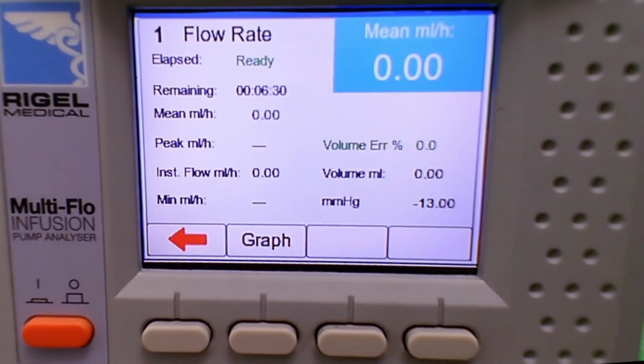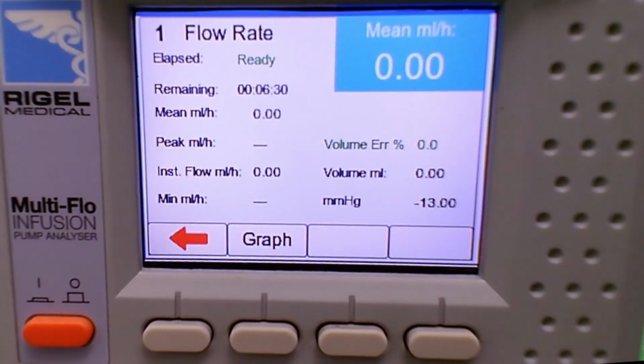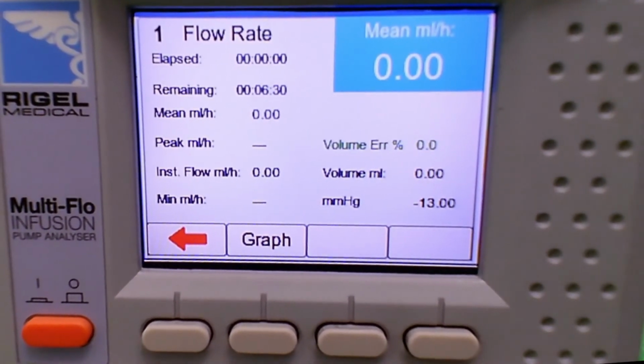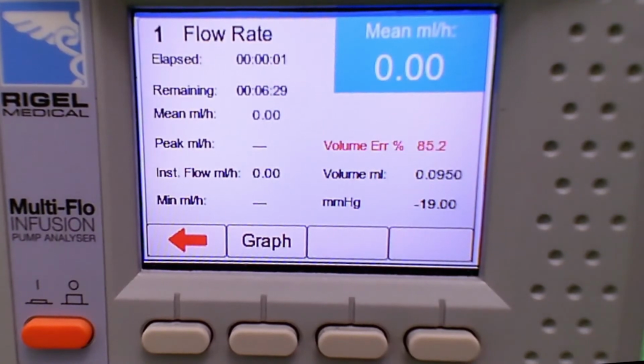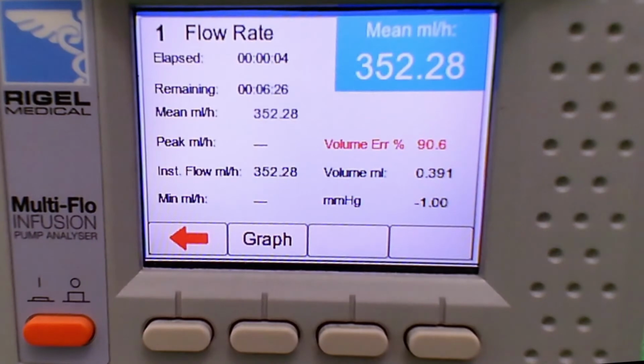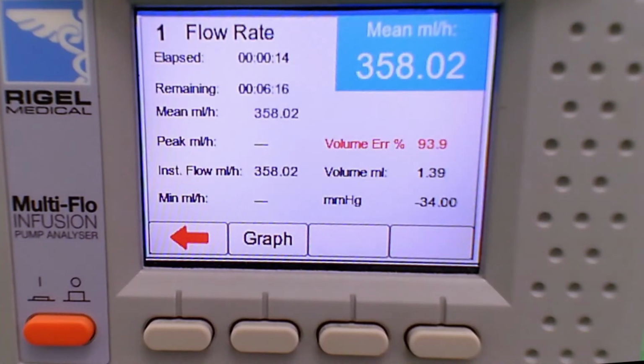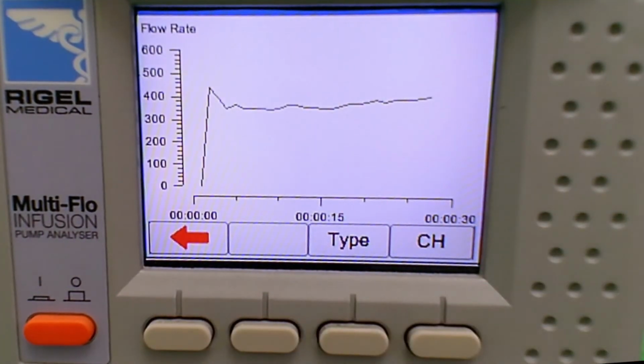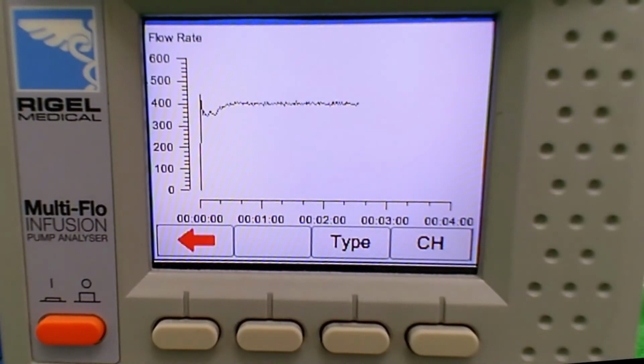Okay, so we're just waiting for the Alaris test to start. Press run on the Alaris SE. Got 400 ml per hour with a 20 ml volume to be infused for the first one, and then once that one's finished, there's an occlusion test, and then we'll do a 40 ml infusion to be in test flow rate test for the second automatic test. Okay, so we've got that initial undershoot for the mean flow, and then there's a slight overshoot before settling down.